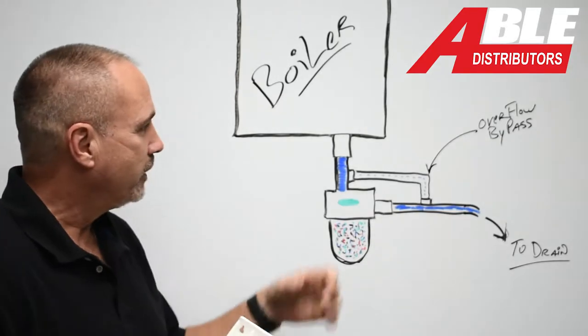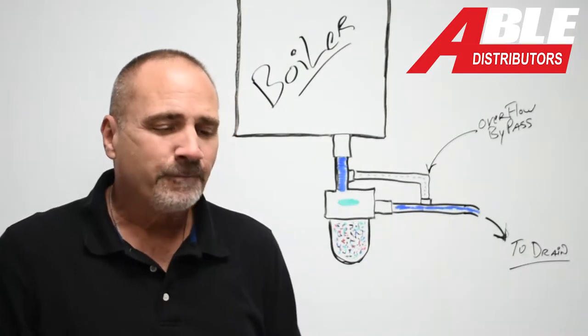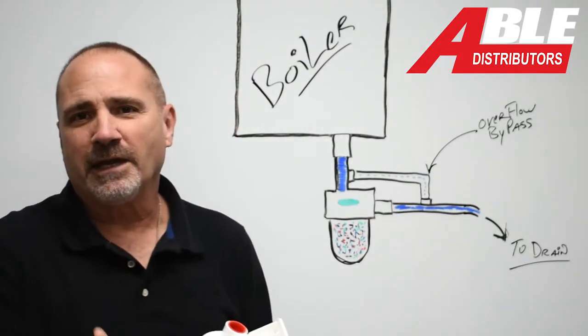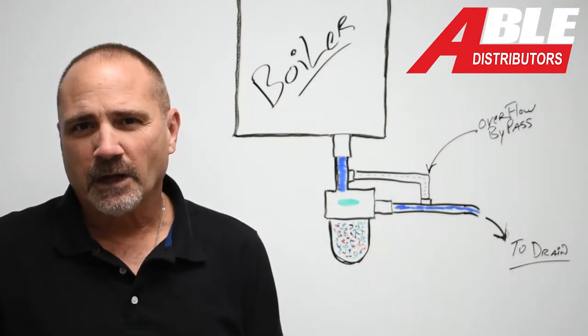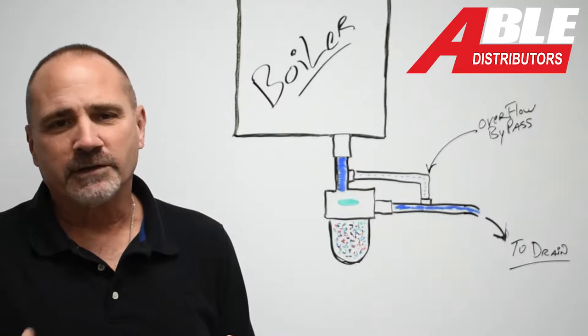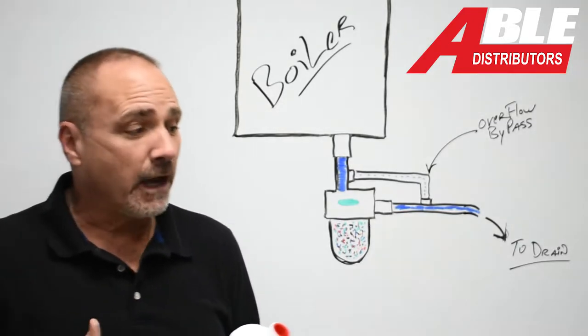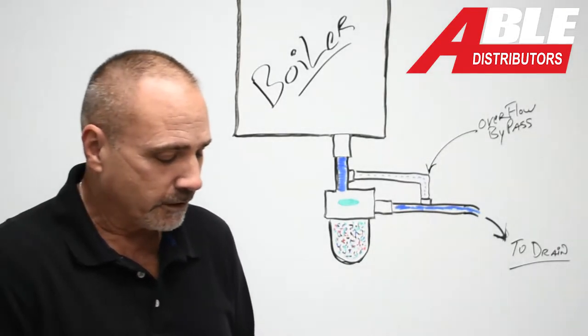We've known for years that we should treat the condensate that comes out of high efficiency equipment, furnaces and such. A lot of times furnaces mix with ACs, so the water gets diluted in the summertime. But all winter long, if you don't have a humidifier, you're putting very acidic water down the drain. And if you've got a cast iron P-trap in the floor, it's really bad for the situation.